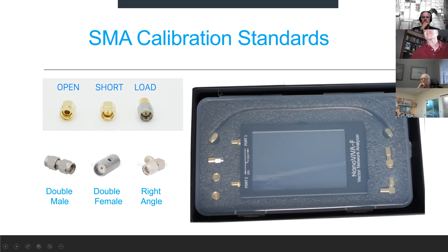First, you open the calibration memory and press reset so that you flush out the old calibration. You open the calibrate menu, which is under it. You connect the SMA open to port 1, wait a few seconds, and then press open. And then you connect the SMA short to port 1, wait a few more seconds, and press short. You connect the SMA load to port 1, wait a few more seconds yet, and press load.